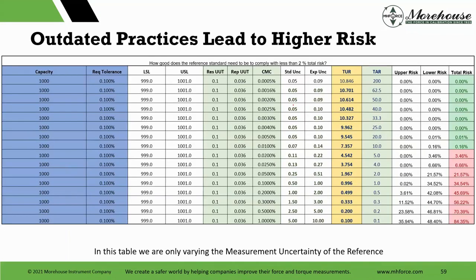So what did we do in this? We are varying the measurement uncertainty. Here we said, let's assume the device is going to be repeatable and have the same resolution, and then just vary this measurement uncertainty column and see what happens. In this scenario, if I wanted 2% risk, assuming my measurement is centered, this is basically saying I need to find a lab that is somewhere between this 0.01 and 0.02 or better to make this measurement. You can back calculate what you need to be, but that's what it's saying. Of course, if I want more elbow room, then I find a lab with much lower uncertainty than that.